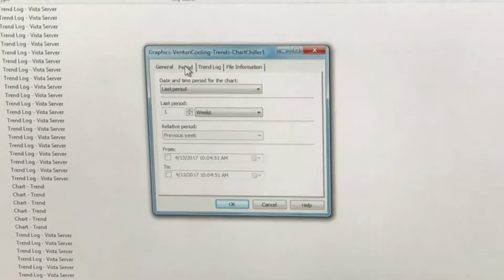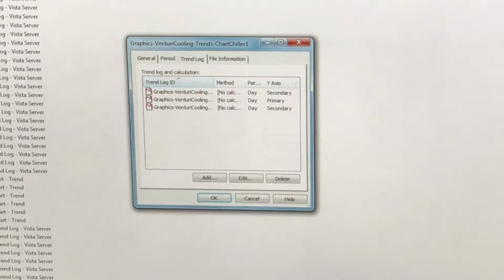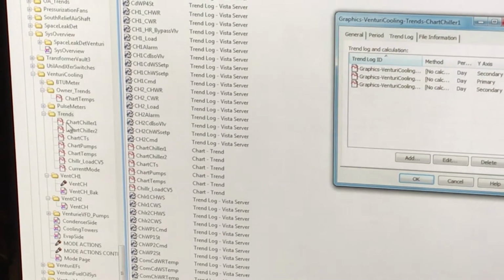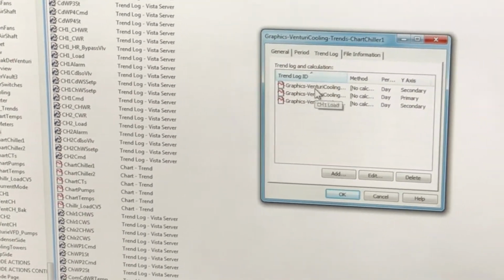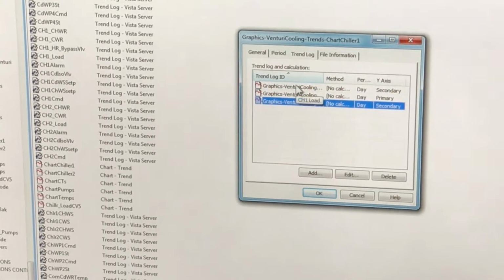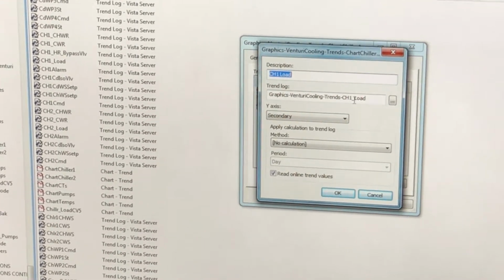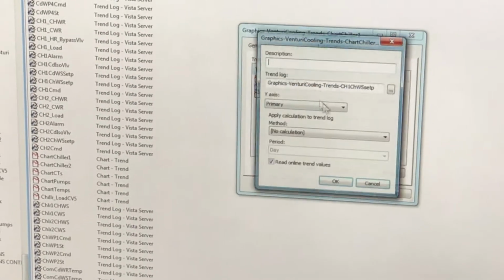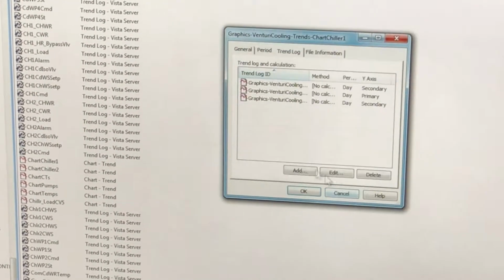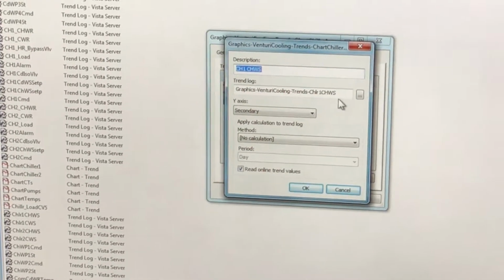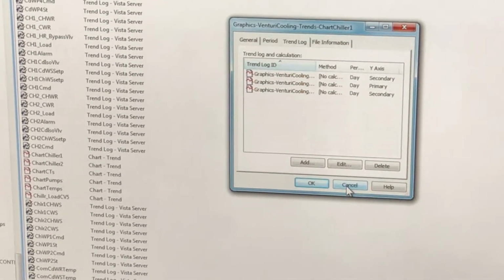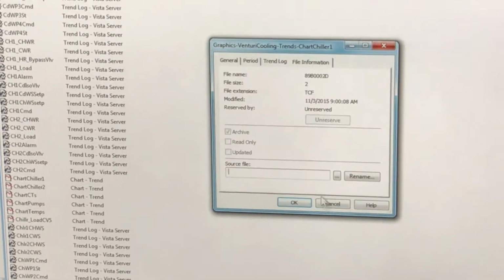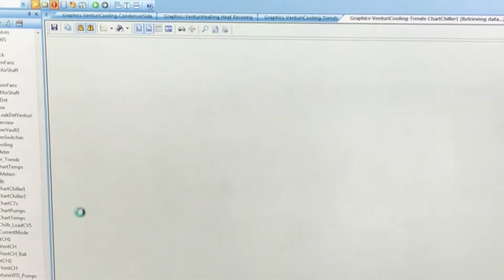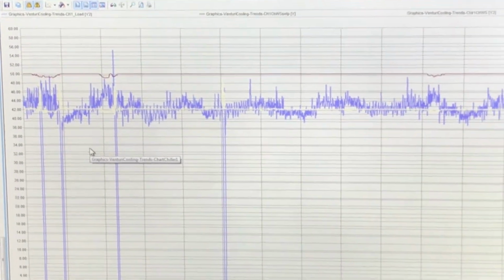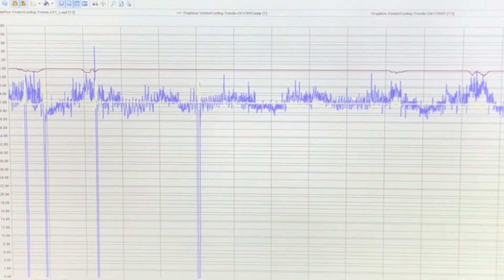So you have the chiller alarm right now, this chiller 1 trend. See the little squiggly line? That means it's a chart. And on that chart, you have 3 points that somebody has added. They have a CH1 load, CH1 Setpoint, CH1 chill water supply. So that is how you create trends like this. You add those points to a trend chart.